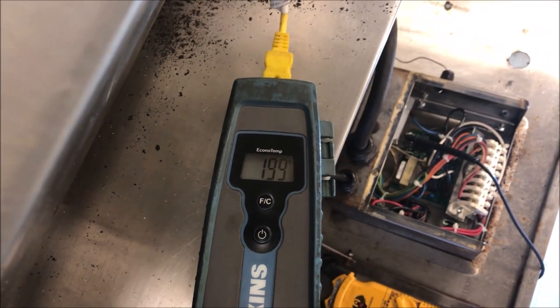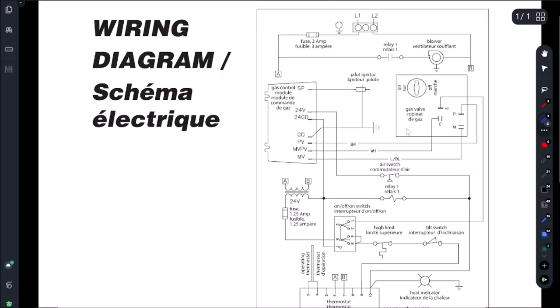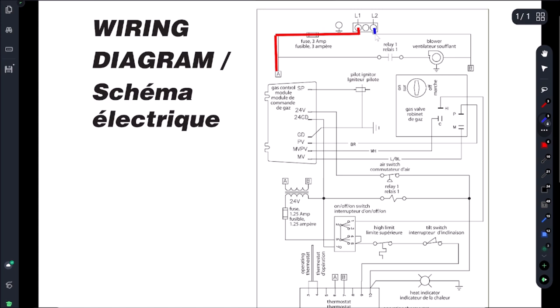So let's go ahead and pull up a schematic and see what's going on. Alright, let's map this bad boy out. We come in here off our L1, coming through a 3 amp fuse, and then our L2 which is actually a neutral is going to make our B terminal hot. Our B terminal is right here.